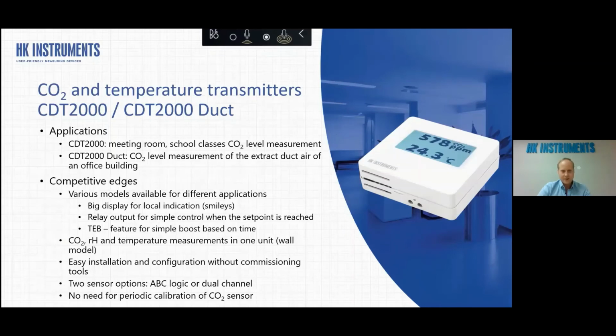So we have this CO2 transmitter for rooms and also for the duct. With the duct, you can get the CO2 levels from a bigger area than just one room. And in the CDT 2000, we have as an option this big display, which is very good for COVID-19 indication in the school classes, because the display is a big touchscreen and you can get smileys to indicate if the levels are good or not. And then we also have an option for the relay output. It's like a simple control when the set point is reached.